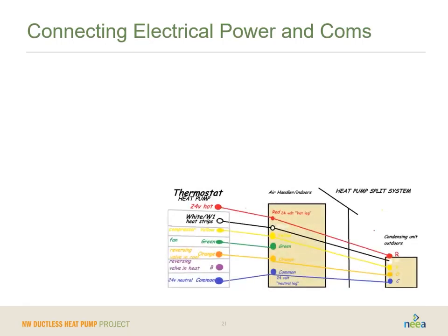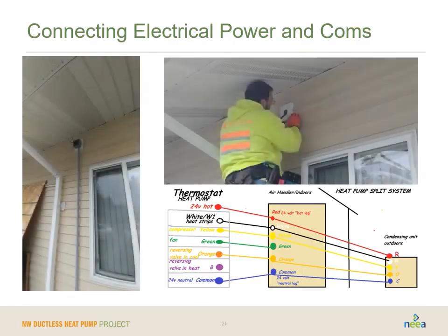There is going to be some connecting of electrical and for both power and communication so that the wand inside actually controls and sends messages to the outdoor unit and the indoor unit. So you're going to need to be thinking about this, and this may require that you either subcontract an electrician or you have an electrician on staff to be able to handle this work. And of course, follow all proper codes and laws when handling any electrical equipment.